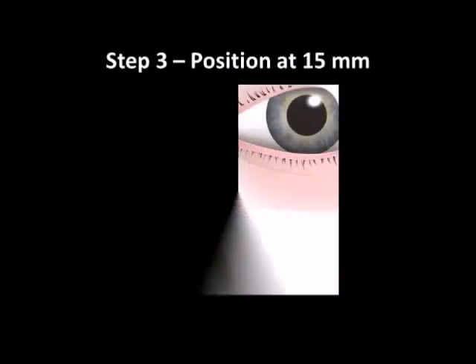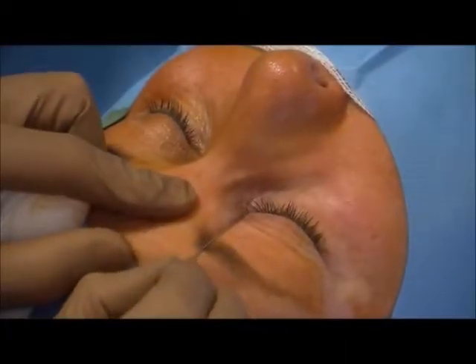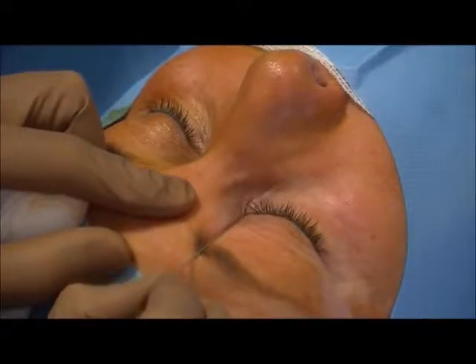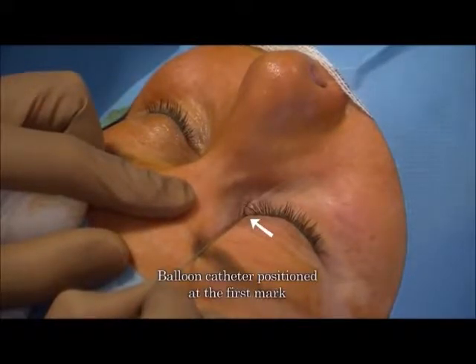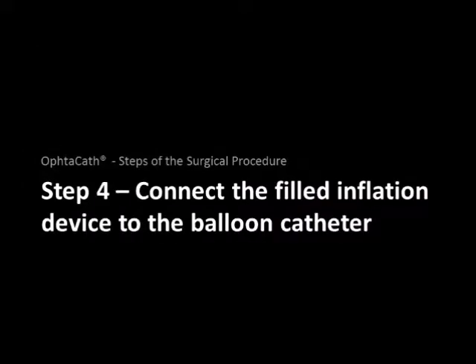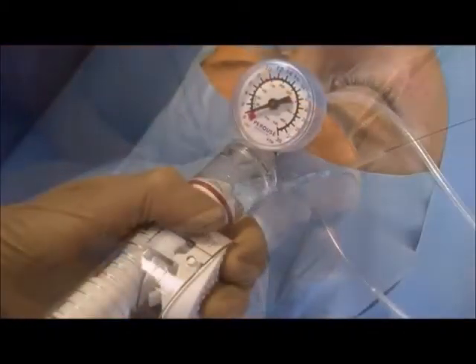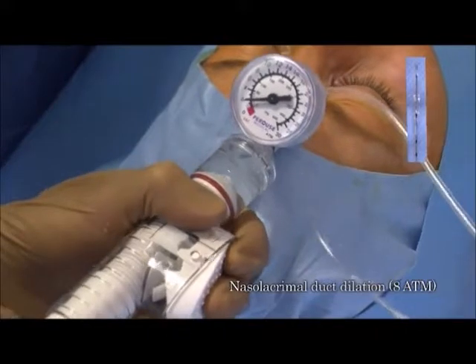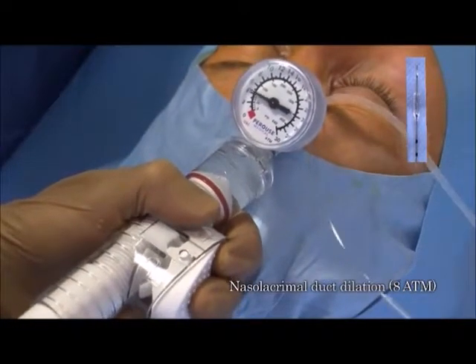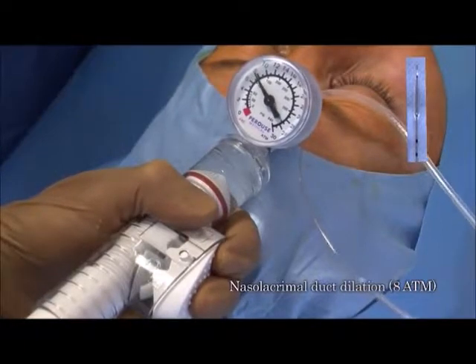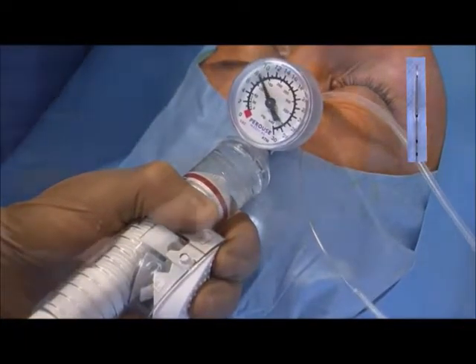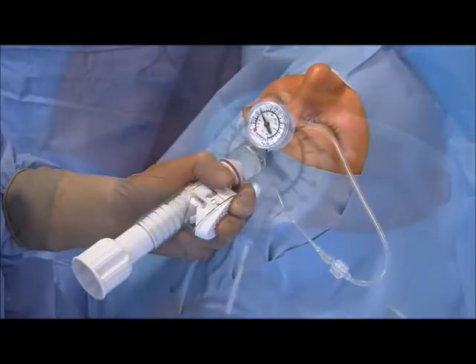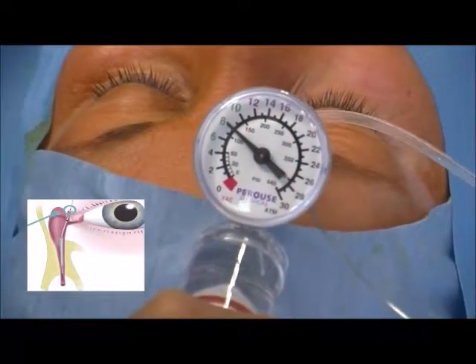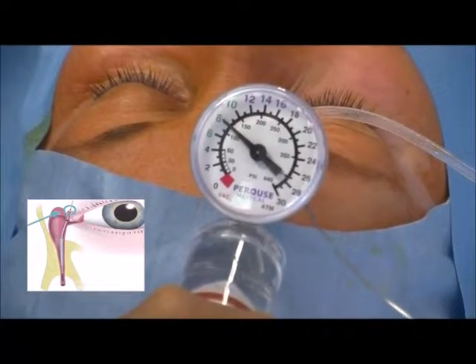Step 3, the surgeon will then pull the balloon proximally and align the punctum with the marking located at 15 millimeters proximal to the balloon. Repeat this step on the other side if bilateral case. Step 4, connect the filled inflation device to the balloon catheter. If in a bilateral case, connect to both catheters. Always point the inflation device downward while inflating. Slowly and gradually turn the rotary handle clockwise to a fill pressure of 8 atmospheres and maintain that for 90 seconds.